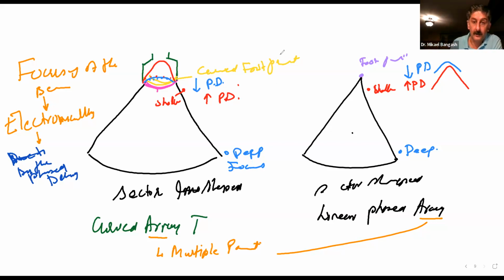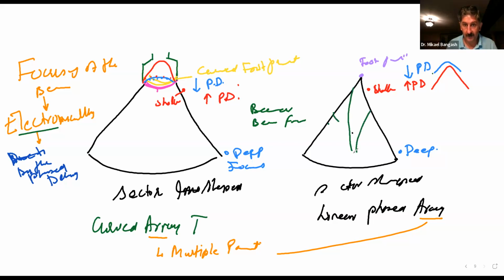And where all this electronic control is happening, whether that was the steering, because even the steering of the beam was electronic, but also the focusing, that would be in the beamer or beamformer. Where we mainly say, if we had a short phase delay, produced in the beamformer, it was going to produce a beam that will end up getting to its narrowest point at a greater depth.